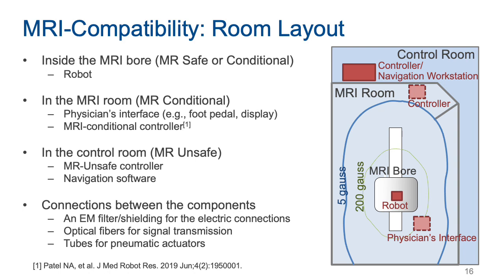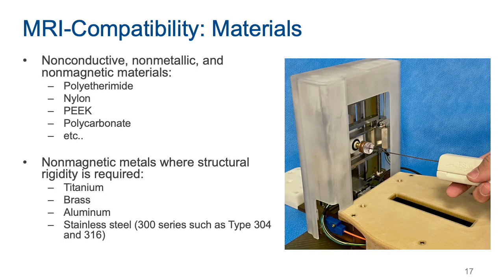These components are often connected by electric cables to exchange signals and information. These cables can transmit EM noise from outside the environment into the MRI room, causing noise on the MR images. If that's the case, it is important to apply appropriate EM filters or shielding to those cables. Some systems use optical fibers for signal transmission to prevent introducing EM noise into the MRI environment. To make the device either MR safe or conditional, we have to choose the materials very carefully. Ideally, those devices are made of non-conductive, non-metallic, and non-magnetic material, such as plastic.